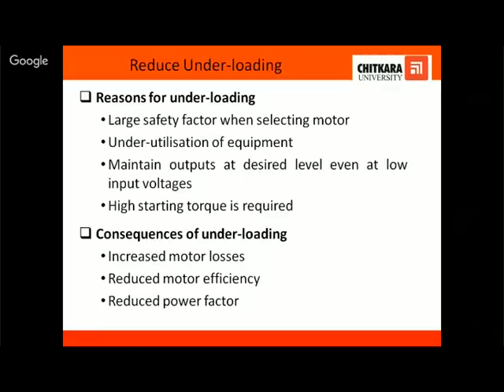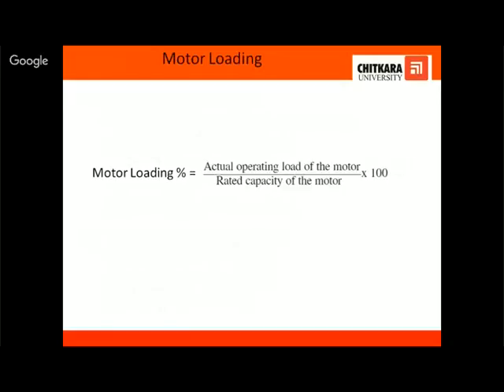That is why we need to understand the speed-torque characteristics of the motor. Instead of choosing a high size motor, choose a motor which has a high starting torque, but the motor should be as per your load rating. So what are the consequences? The motor losses increase, the efficiency goes down and the power factor goes down. And when we have to calculate the motor loading, this is how it is calculated: actual operating load of the motor divided by the rated capacity of the motor. This is how we work out the percentage loading on the motor.